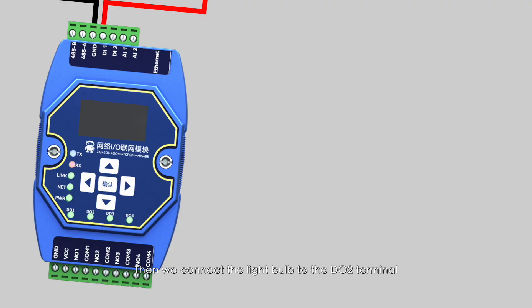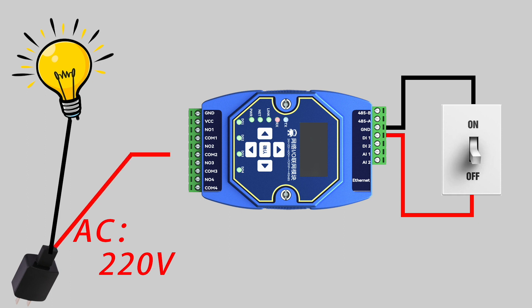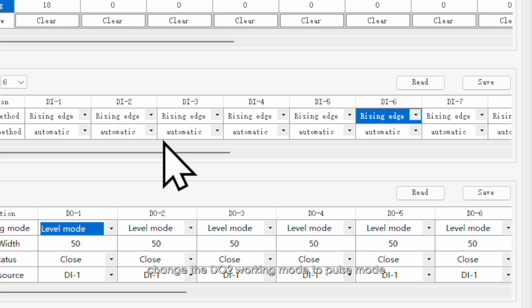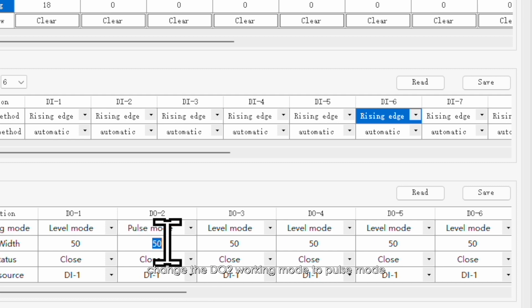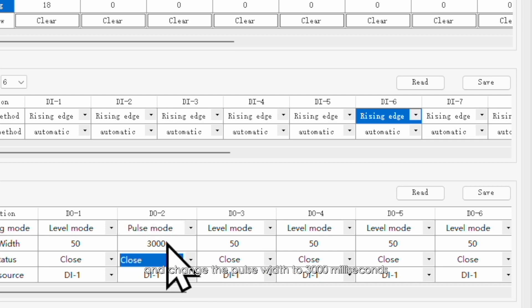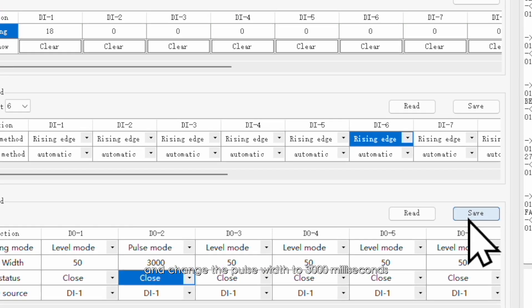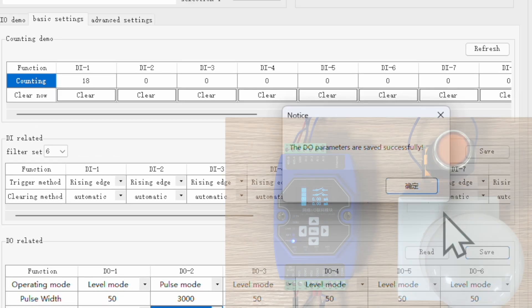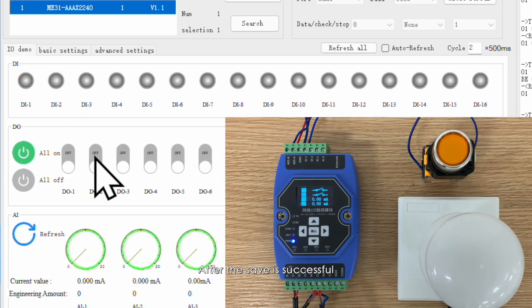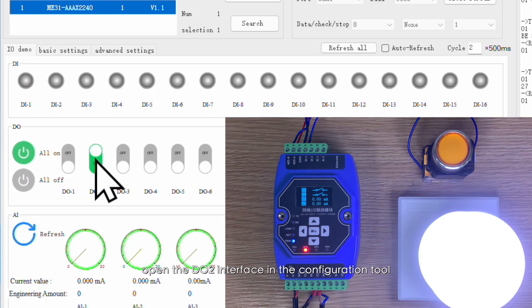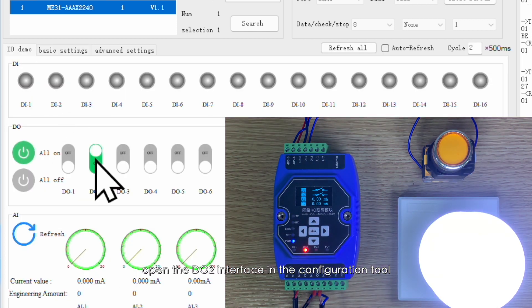Then we connect the light bulb to the DO2 terminal. Open the configuration tool, change the DO2 working mode to pulse mode, and change the pulse width to 3000 milliseconds. After the save is successful, open the DO2 interface in the configuration tool, and you will see that the light bulb will automatically turn off after three seconds.